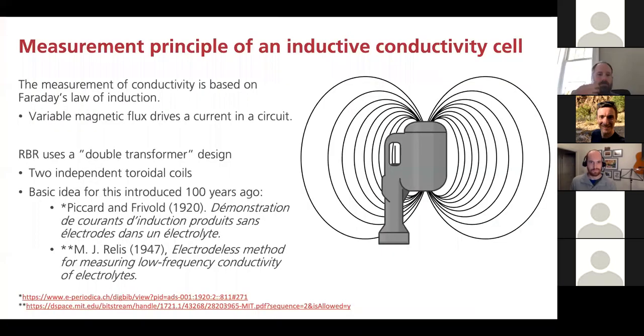So we start off by taking a cell and putting two ferrites in it. One is in the bottom of the cell, and it is the drive. And the second one is in the top of the cell, and it is the pickup. And the only way that this pickup sees anything is if there is a conductive loop that attaches those two ferrites together. And because there's no conductive loop in the cell design itself, the reading will be exactly 0 when the cell is in air.